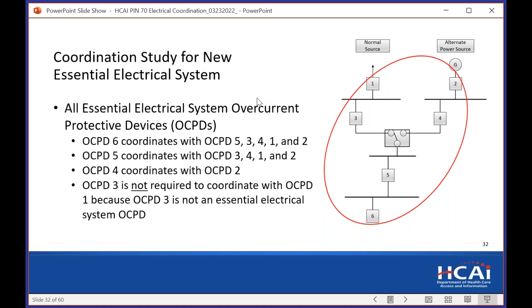We talked about this earlier. What is the scope of electrical coordination? So we know it's all the way from your branch circuits, even your 20 amp single pole breakers, all the way up to your generator breaker. And it's all the way up to your normal side, with the exception that your normal side feeder and main breaker do not need to coordinate because they're not part of the essential electrical system.